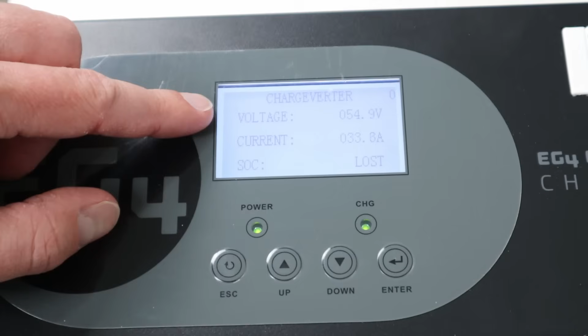Let me just go into the settings here to see what I have this set to. So voltage is 55, state of charge start is 50%, battery start is 49 volts, current is 50 amps, state of charge stop is 100%, and battery stop is 56 volts.